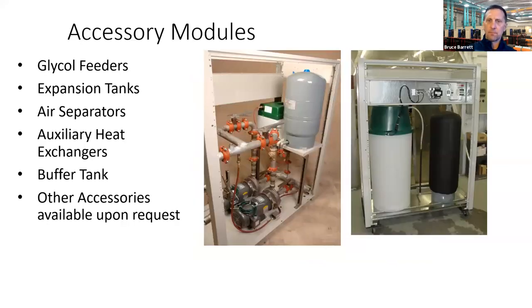Just a different shot of some mini glycol feeders and our larger glycol feeder for obviously larger jobs that have larger capacity. If the system has a small leak, it's got to make up water. It's got an alarm on it. We can do auxiliary heat exchangers, again, multiple pumps. Just about anything you want, we can do in the factory under a controlled setting and meet your design requirements.